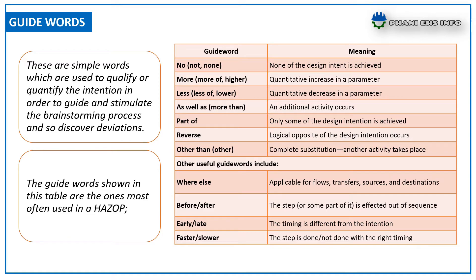Further guide words include: PART OF — only some of the design intention is achieved; REVERSE — the logical opposite of the design intention occurs; OTHER THAN — complete substitution, where another activity takes place, an unusual activity occurs, or an uncommon condition exists. Other useful guide words include WHERE ELSE, BEFORE/AFTER, and OUT OF SEQUENCE.